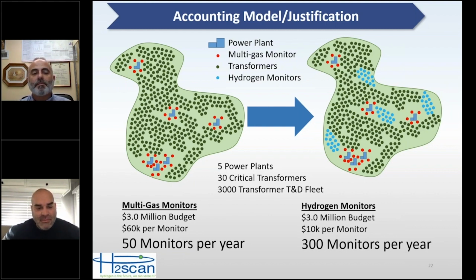Anyway, you've got a number of power plants in the region, and generally with your multi-gas monitors, the first place people put those is at a power plant, because those generator step-up transformers are critical. If they lose one of those transformers, they're going to lose some amount of generation, which can run into millions of dollars a day in losses. So those are very critical transformers, and typically people today are putting multi-gas monitors on their generator step-up transformers. But for the other transformers across their T&D system, because of the expense, it's difficult to really cover a lot of them.